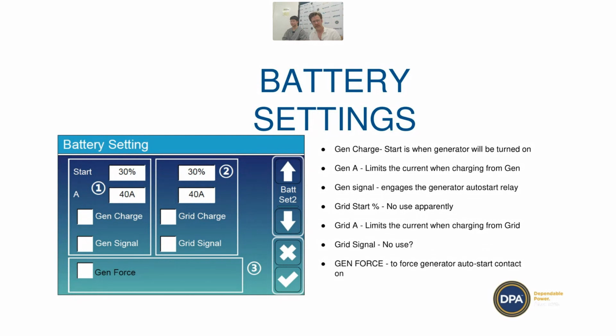After we've done that page, we're going to go into the next battery settings page by pressing the down arrow. And this is where you're going to set up your disconnection and charge rate settings for the grid or for the generator. So what we're setting here, if we just assume that we're on grid for now, we're just interested in this right-hand column here, which is grid charge and grid signal. And so what this is saying is that if the battery gets below 30%, then it's going to charge from the grid. And it's going to charge all the way up to the top. And it's going to do it at a rate of 40 amps. And that's a DC value. But it will only do that if you have grid charge ticked here. Grid signal isn't really used, so don't worry about that.